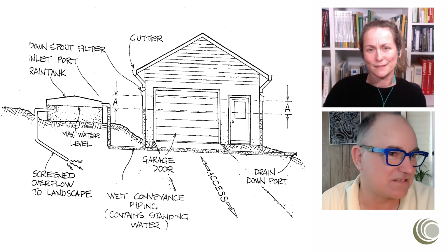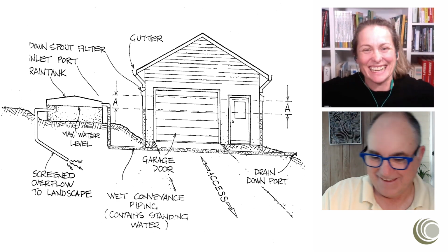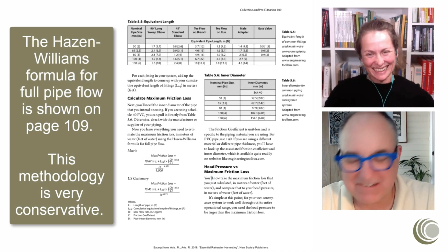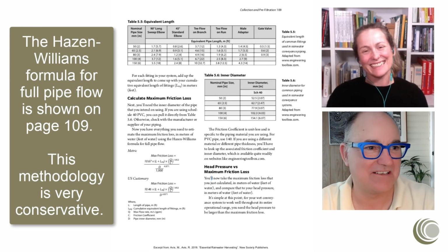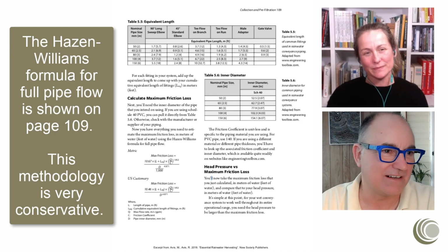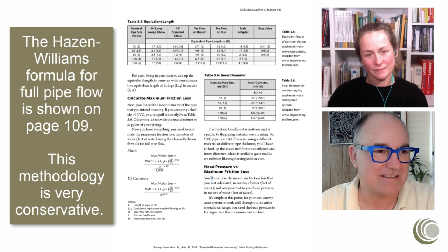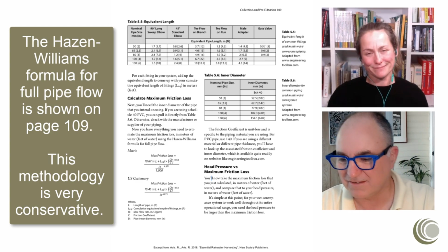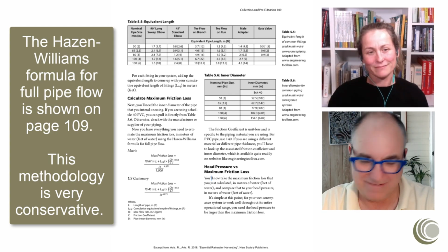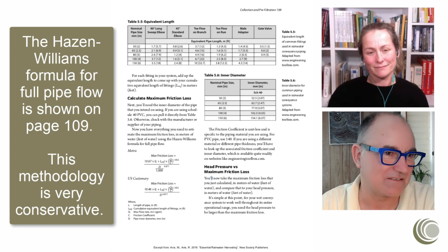So a foot. And you don't have to pull out the Hazen-Williams formula to calculate it. I know you're a bit nervous about that before, especially when I said there's bend losses and entry losses and exit losses. I did some back of the envelope thinking about this just now, and I realised that these are quite small, and we've been advising people in Australia that if it's greater than 300 millimeters above, it's most likely going to work properly.